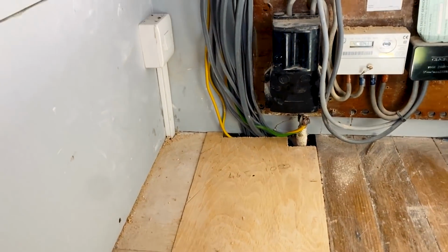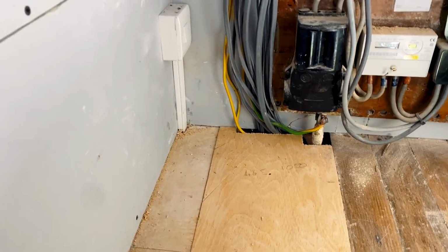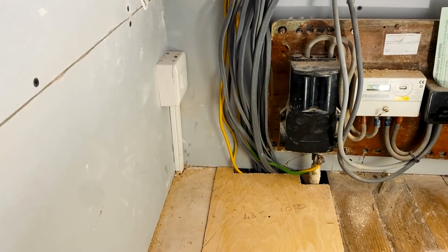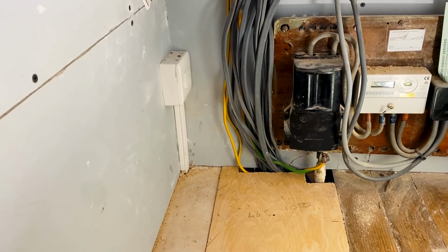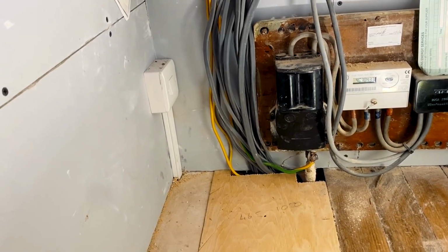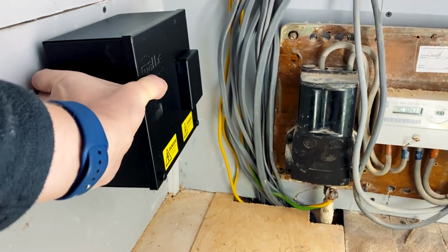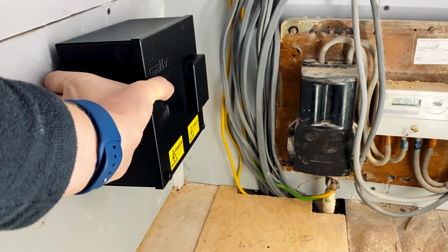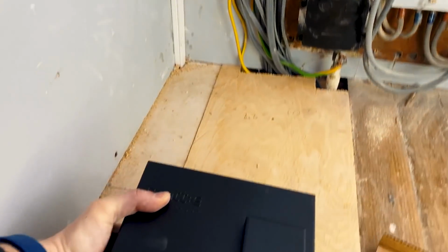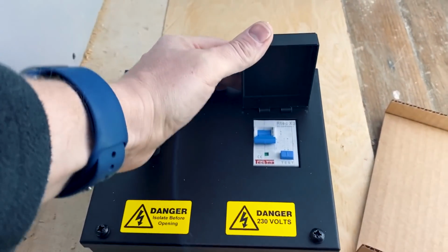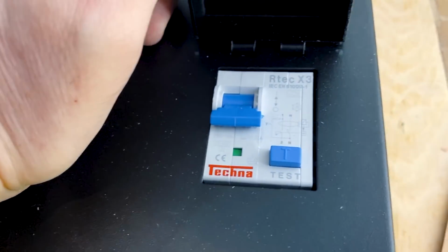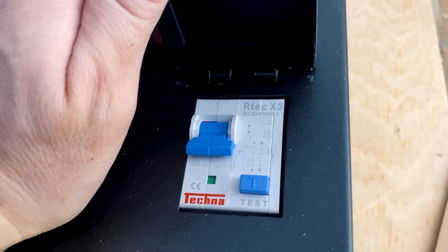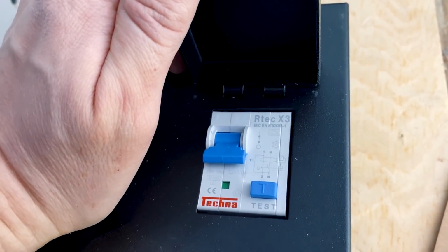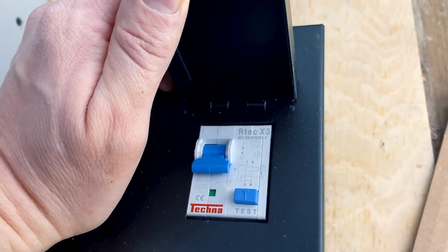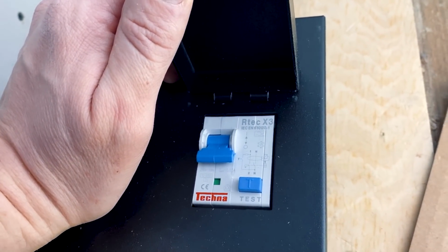The EO Mini Pro has 6 milliamp DC fault protection in it, so it only needs a type A RCD. This is the Techna device, and it integrates, as I said earlier, a type A 40 amp RCBO, double pole, so that provides the overcurrent protection and RCD protection that we need.